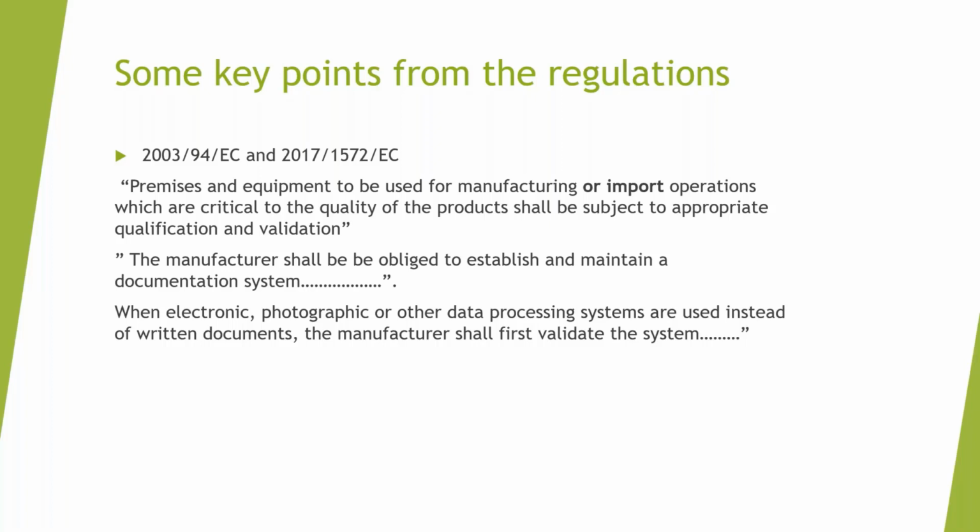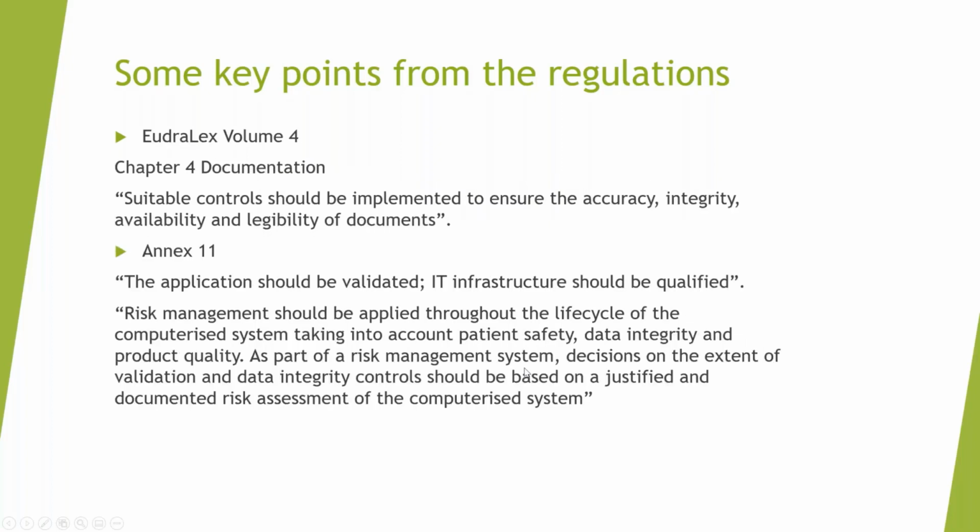It also says that when electronic, photographic, or other data processing systems are used instead of written documents, the manufacturer shall first validate the system. So there's a little bit of a theme here that a laboratory will be using a lot of electronic analytical equipment that has to comply with regulatory requirements and needs to be qualified and validated.